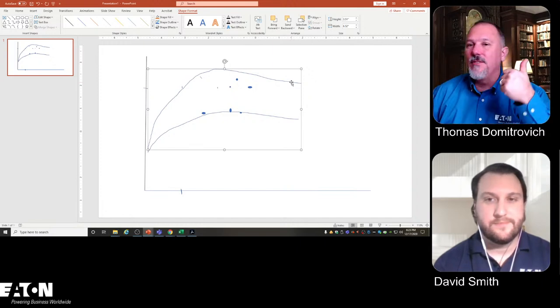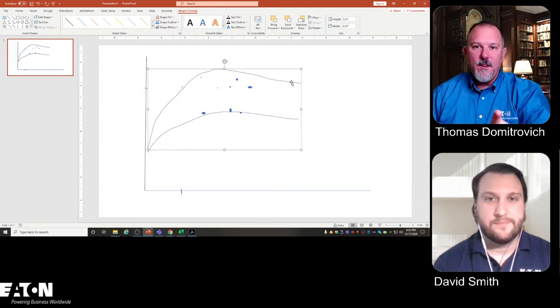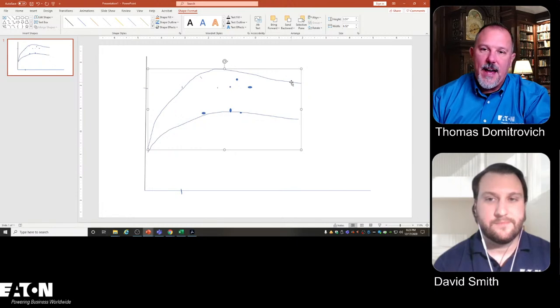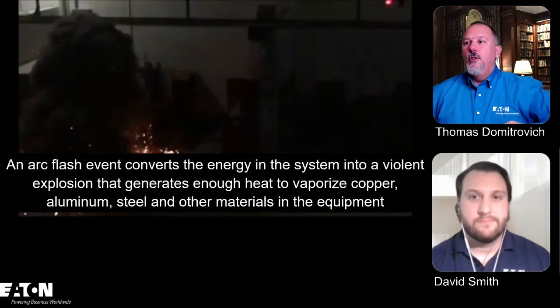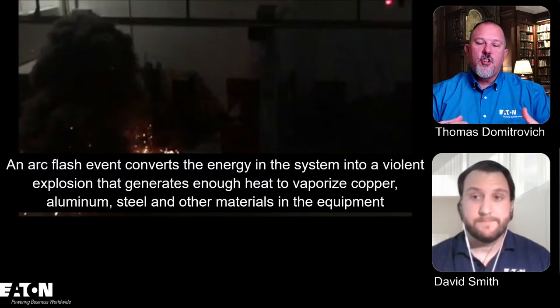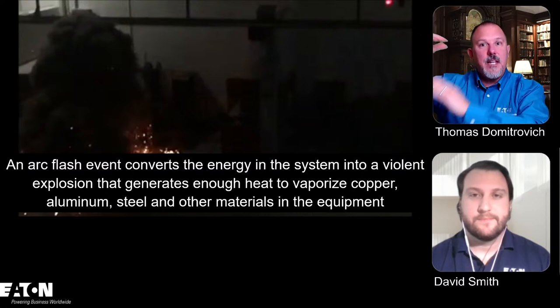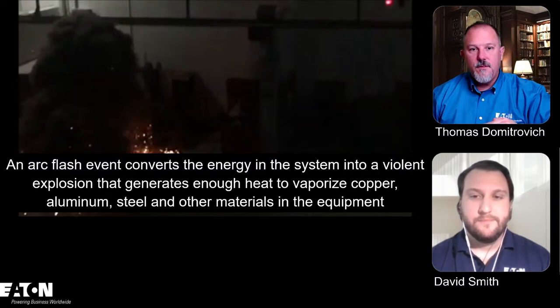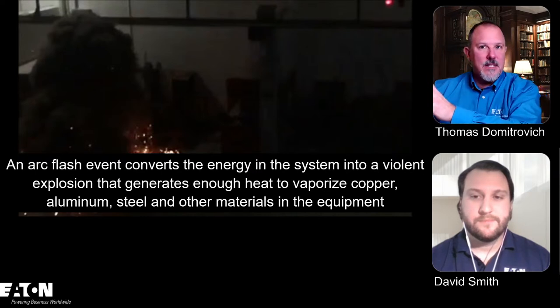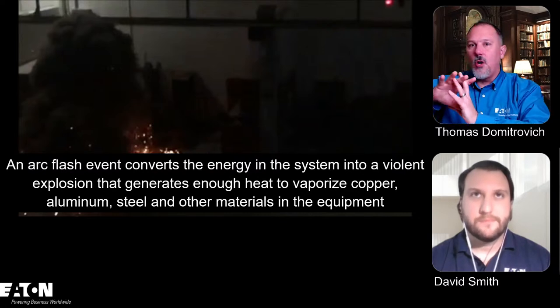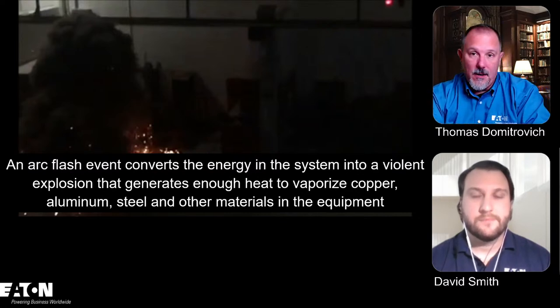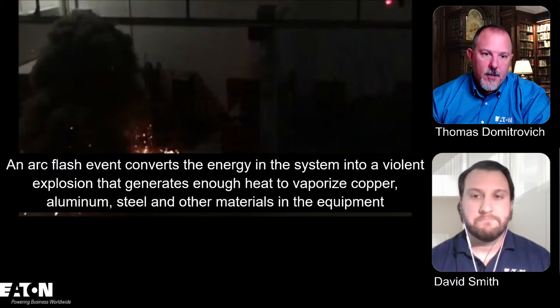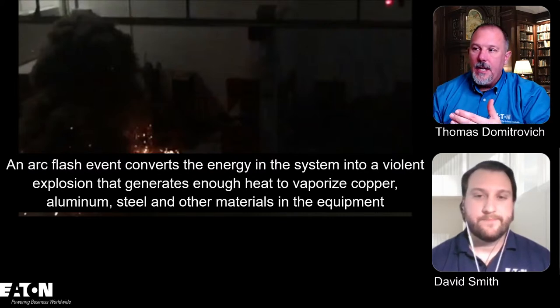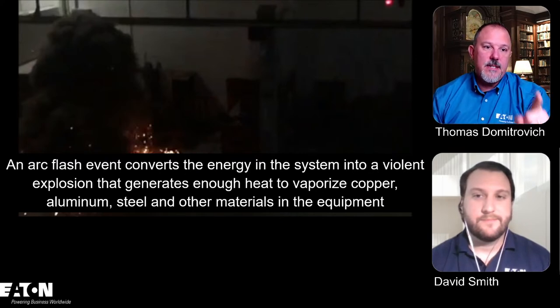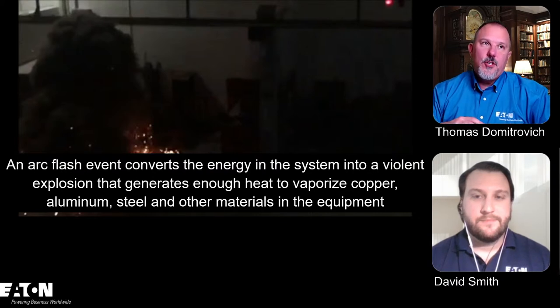What we did in the 2002 version of 1584 was we calculated one version of arcing current and we just did 85% of that and got the lower number. So his efforts were to create the arcing currents. And then he did the same thing for incident energy. He would take each of those arcing current values and their clearing times and determine incident energy based upon that, which was a whole other set of equations developed in a similar manner. So he basically developed the equations to calculate a minimum and maximum arcing current. So that's how I can answer Daryl's question to say, yes, it's possible to calculate them.